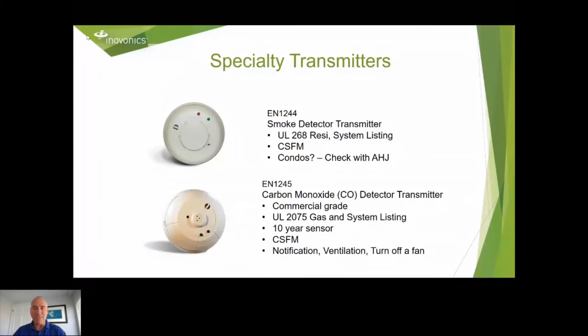But we do have EN1245, that's our carbon monoxide. It's for hospitality. It is a commercial grade sensor. UL 2075 is a system listing, which means it can participate, for example, with an appropriately listed alarm panel so that when it is tripped in the presence of excessive CO levels, it can alert people to get out as well as initiate air movement. That's a 10-year sensor. So that's our System Sensor CO with Inovonics built in, EN1245.